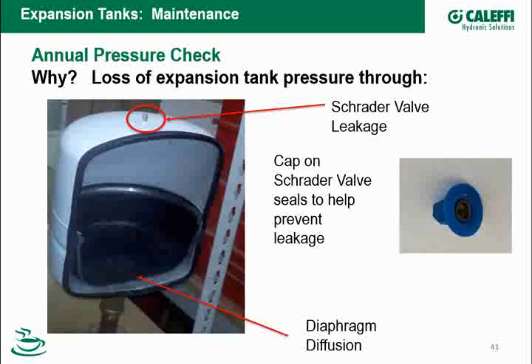Very good. And 2 more questions that were related to that. When you do pre-charge them, just to clarify, do you pre-charge them to the static fill pressure? Is that correct? That's correct. And you just reminded me, when you check the pre-charge, you have to make sure that there's no water on the backside of the diaphragm. Otherwise, you won't be reading pre-charge pressure. You will be reading system pressure. So the pressure across that diaphragm equalizes. If my system is at 18 psi, I check the pre-charge on the tank. The tank's going to show 18 psi as well. Okay, very good. Thank you.